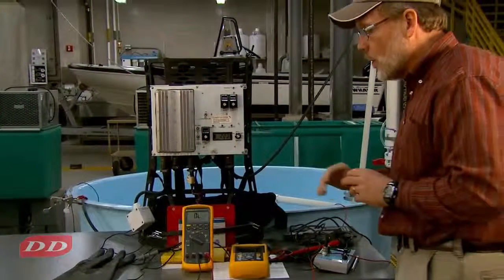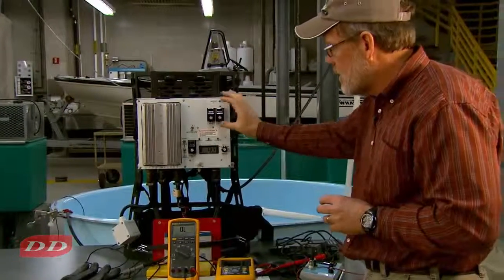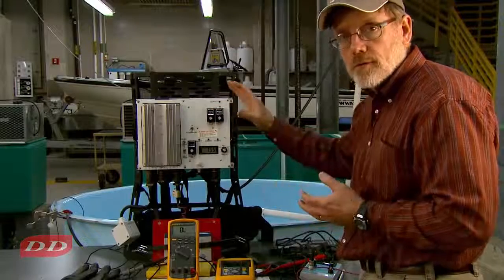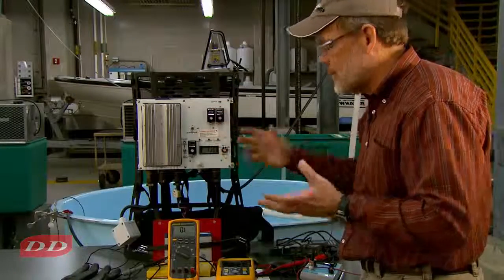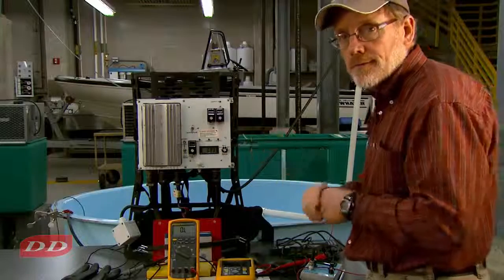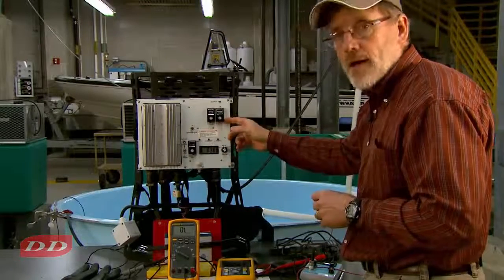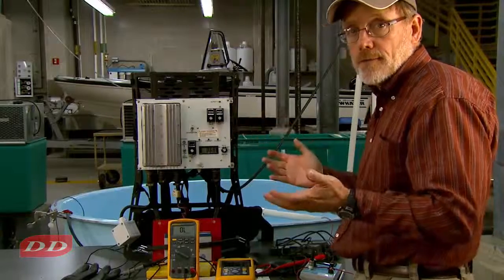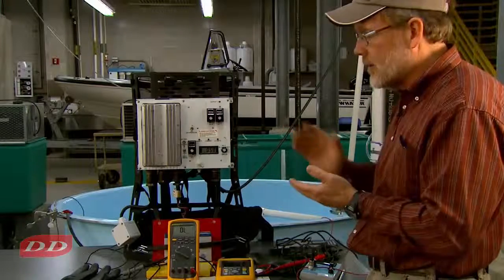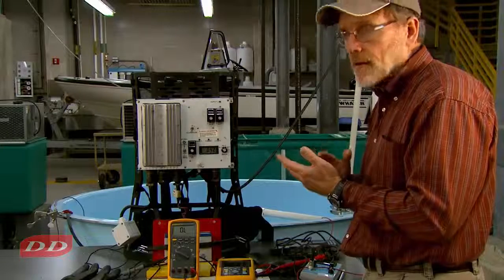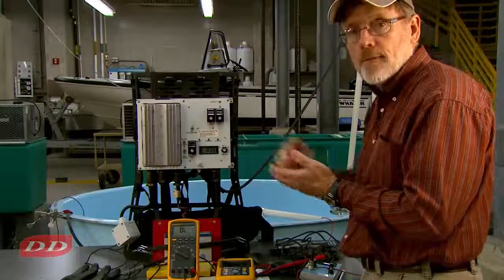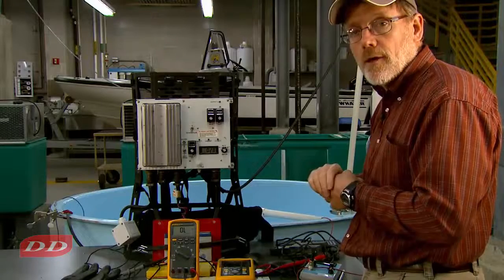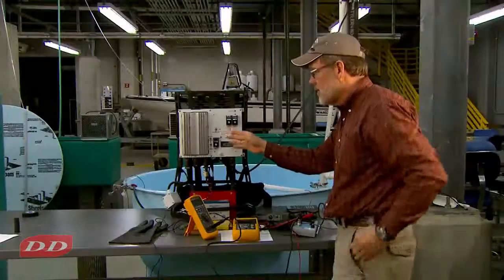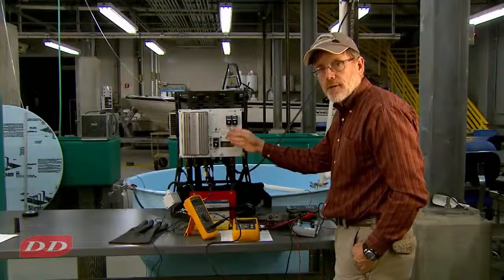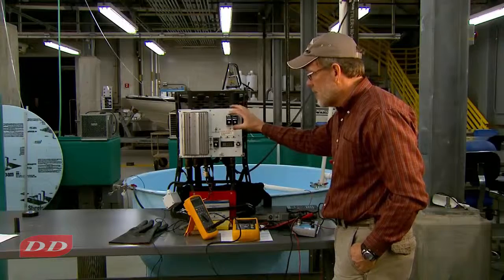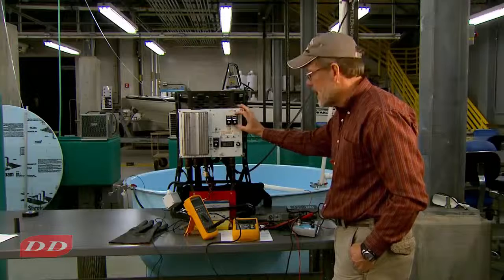So you can go through the frequency range in this particular unit from near 0 up to 1,000. You can go through the duty cycle range in this unit from about 1% to 50% and do exactly like we did for voltage, go through various increments and check to see what the calibration checks out to be. So we've looked at the calibration of voltage, and we've made a measurement comparison for frequency and for duty.